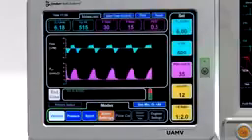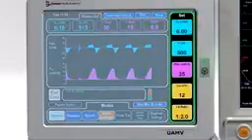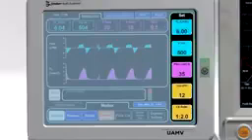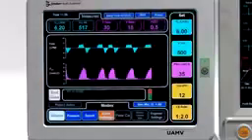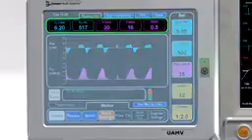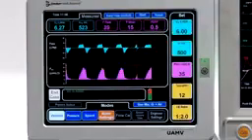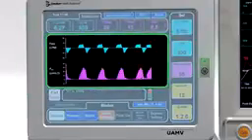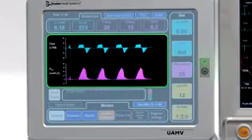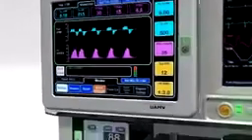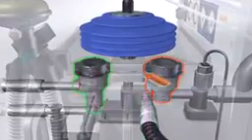Delivery settings are grouped together. Volume, pressure, rate, and IE ratio are individually adjustable. Output measurements appear at the top and show volume, pressure, and PEEP values. Several graph options are available to plot flow and pressure versus time, as well as compliance loops. Anesthetic gas is delivered to the breathing block and through the one-way valves and inspiratory limb in the same way as the manual bellows shown earlier.